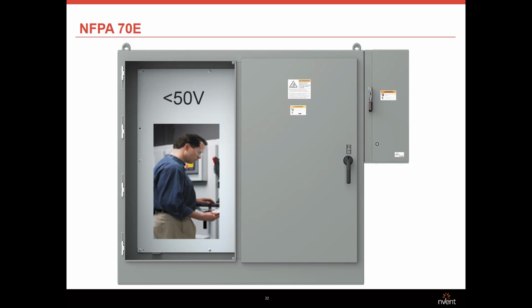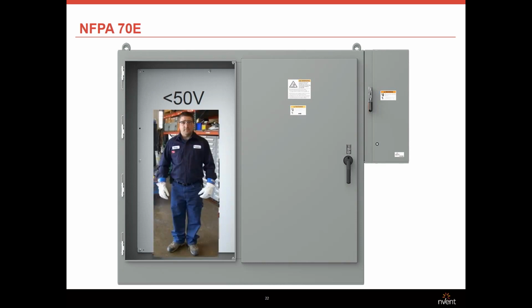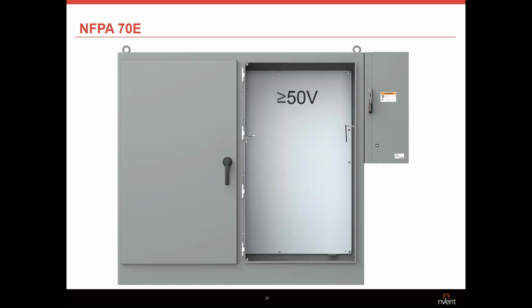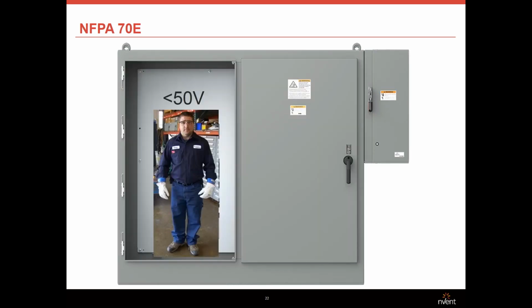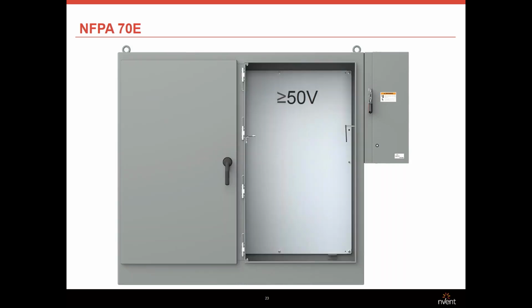Now, while that is the requirement at Hoffman, we practice a higher level of safety for everyone involved. Anyone who is authorized to enter control cabinets is issued Category 2 fire-resistant uniforms and is required to wear them daily. Pictured is Category 2 clothing with safety glasses instead of the face shield. At voltages equal to or greater than 50 volts, the PPE level spelled out on the warning label is required.